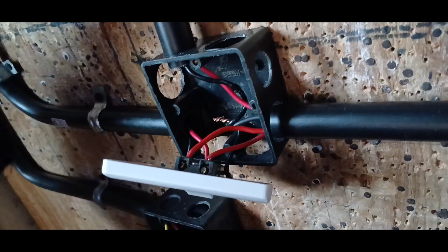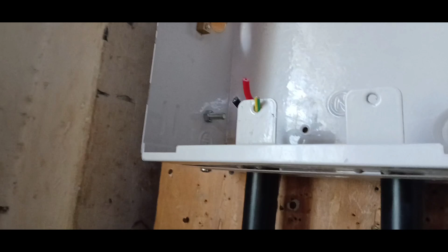Now from here, after you have run your cable from the live, neutral and earth bar. Since this is a socket, we run from the earth bar. We have the other cable here, but for the switch you don't have the earth cable. So the earth cable is here for the socket. So they leave from the 16 ampere circuit breaker to the socket here. This is the socket outlet.